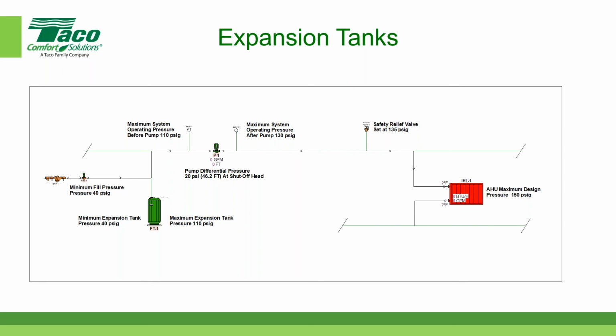Actually, we snuck another question in here. So if I have a 10-story building, would it make sense, even if my mechanical room's in the basement, to put my expansion tank way up on the roof or a penthouse or something? Well, it is possible to put the expansion tank at the top of the building if the mechanical room is at the bottom of the building. However, we would recommend that you run a dedicated line from the expansion tank down to the suction side of the pump that's at the bottom of the building.